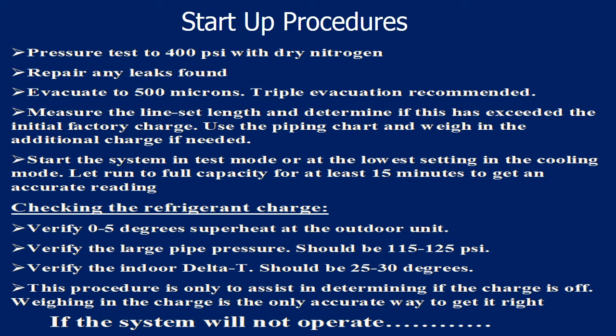Anytime a refrigerant leak is repaired, the entire refrigerant charge should be removed and weighed back into the system according to the amount shown on the nameplate using virgin R410A refrigerant.